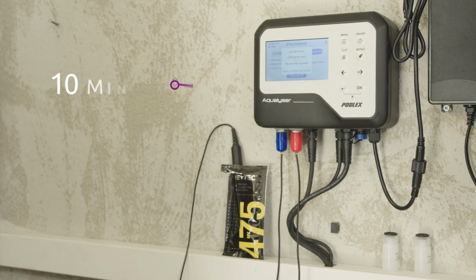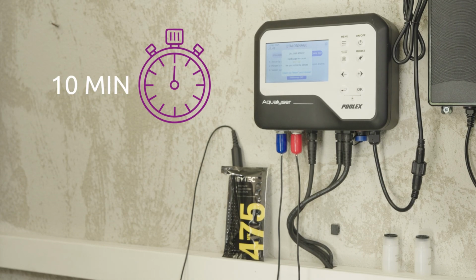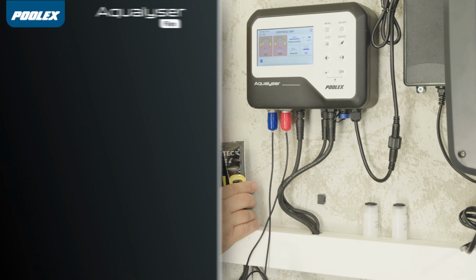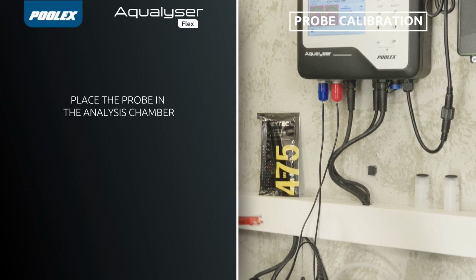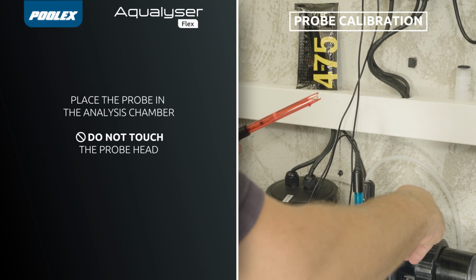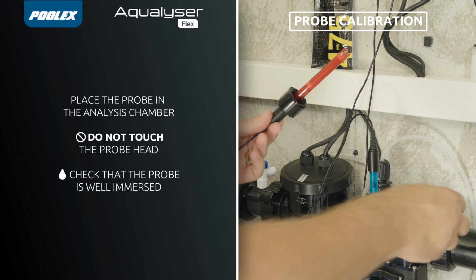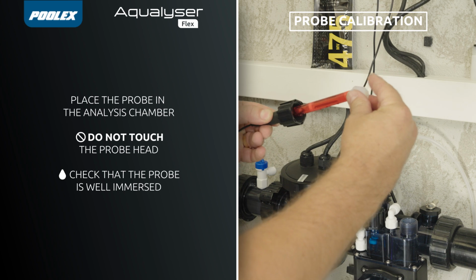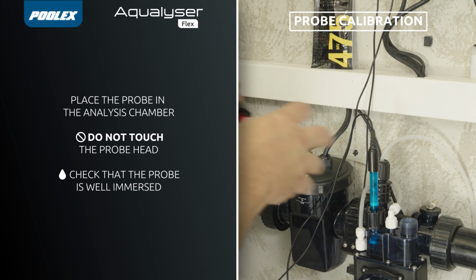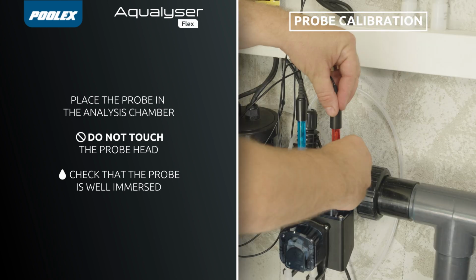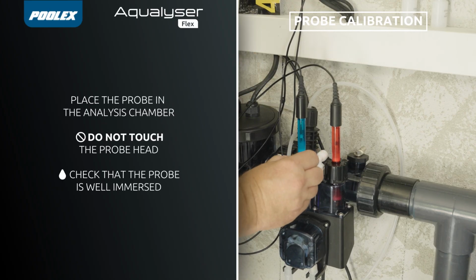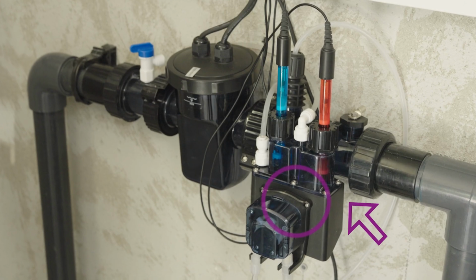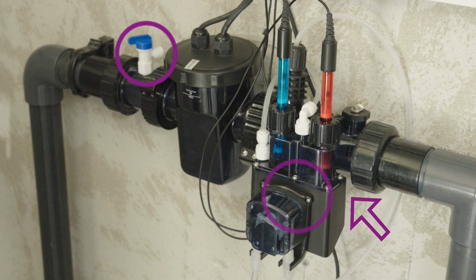Calibration begins. Leave the probe in the solution for 10 minutes. You can now place the probe into the probe holder of the analysis chamber. Warning: do not touch the probe head with your fingers and check that it is well immersed in water. You can now open the inlet and outlet valves of the analysis chamber to supply it.